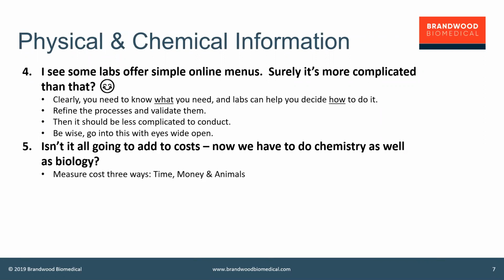I think that the reality is that for a lot of device manufacturers, doing the chemical characterization and the toxicological risk assessment will in fact ultimately reduce the amount of time, money and animals that are expended in the process of establishing biocompatibility.